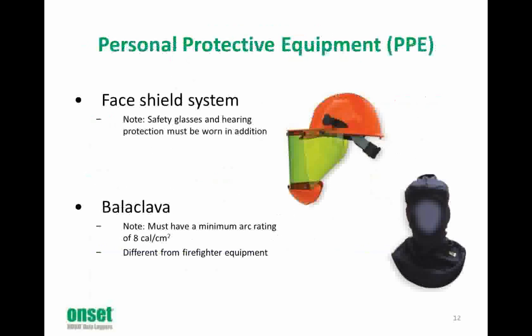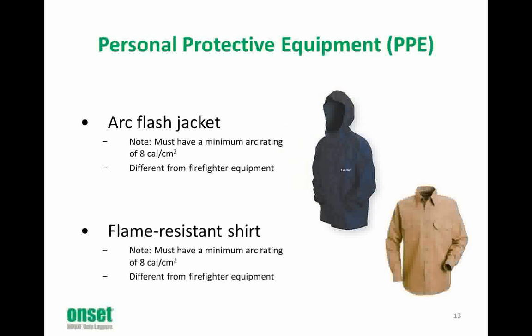So starting top to bottom, we have the face shield system. In addition, we have to wear safety glasses and hearing protection. We also have the balaclava. This is different from the firefighter equipment. This has to have an arc rating of at minimum 8 calories per square centimeter. We then wear the arc flash jacket, again with an arc rating of 8 calories per square centimeter. Or we can wear a flame-resistant shirt, again with the same arc rating.